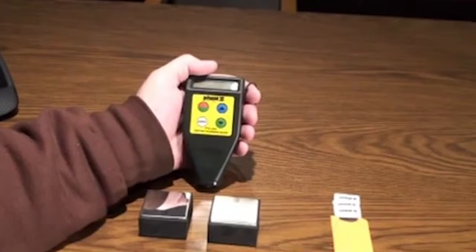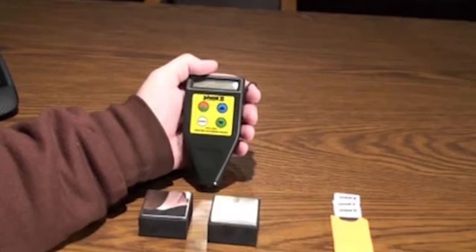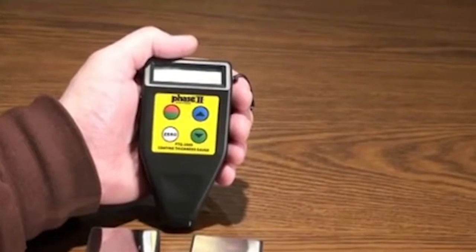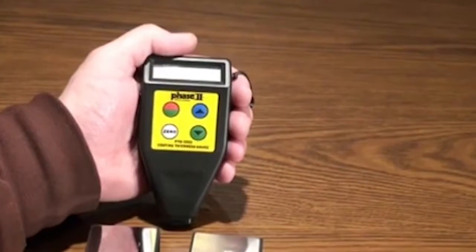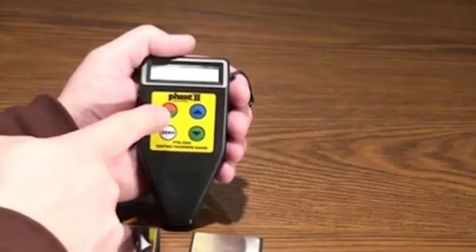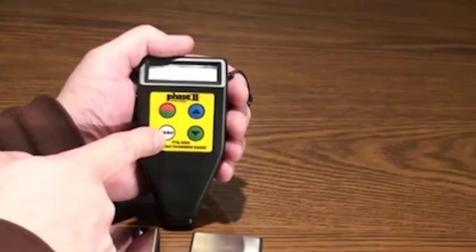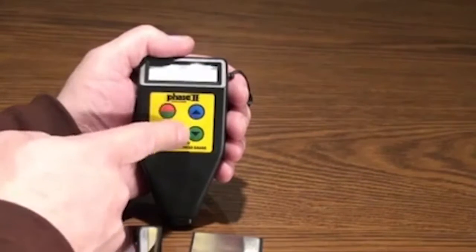Now let's move over to the operation of the coating thickness gauges and how easy it is to utilize the different functions, taking tests, and obtaining readings. As you can see, the keypad layout is quite simple. You have a power key, a zero key, and arrow keys for scrolling.